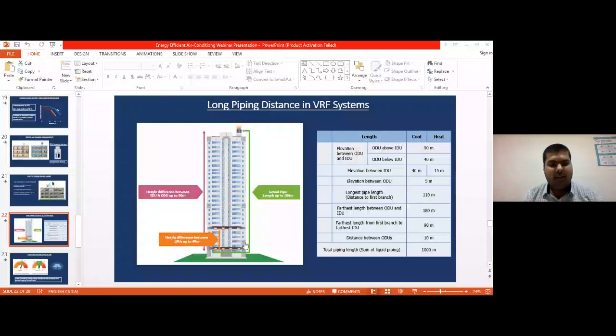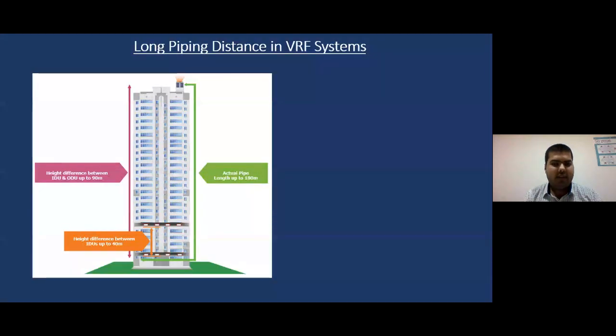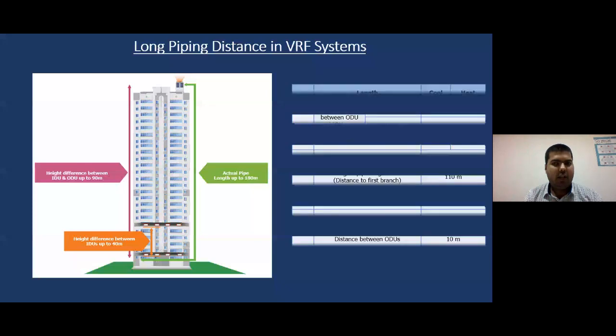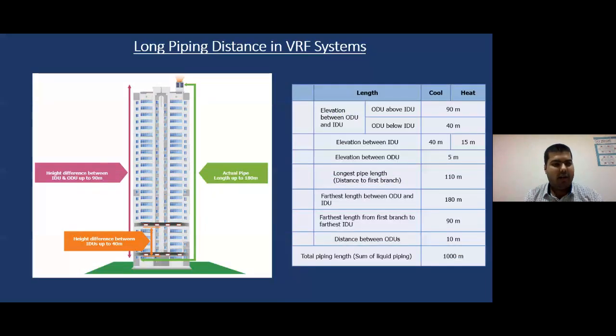Long piping distance in VRF systems. So the beauty of VRF is the elevation between ODU and IDU. It can go up to a maximum of 90 meters, and the overall piping length can handle a total of 1 kilometer. That is the most important feature of VRF, so that your exterior does not go for a toss in a high-rise building.